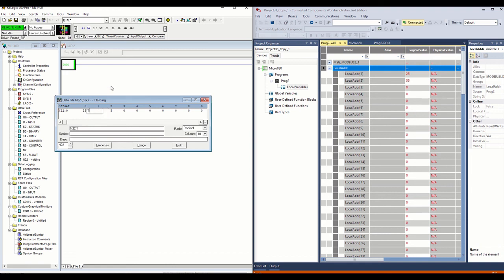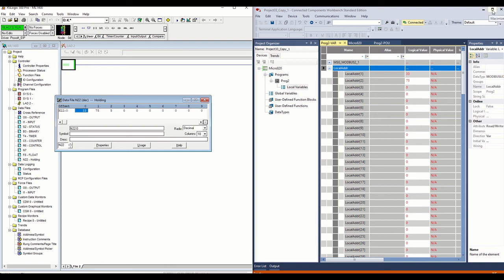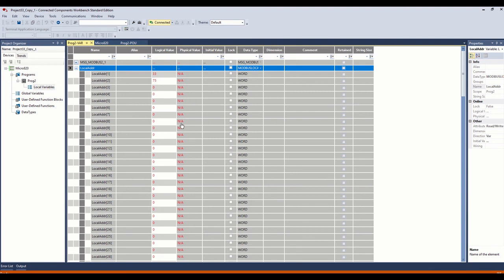If we were to change this to 75, we should see our local address over here change to 75. So let's hit enter. And there it is. So we are reading data. We change this one, see it over there. Yep. So that's how you're reading data over the Modbus from a MicroLogix 1400 to a Micro 820, and the Micro 820 is acting as the master.